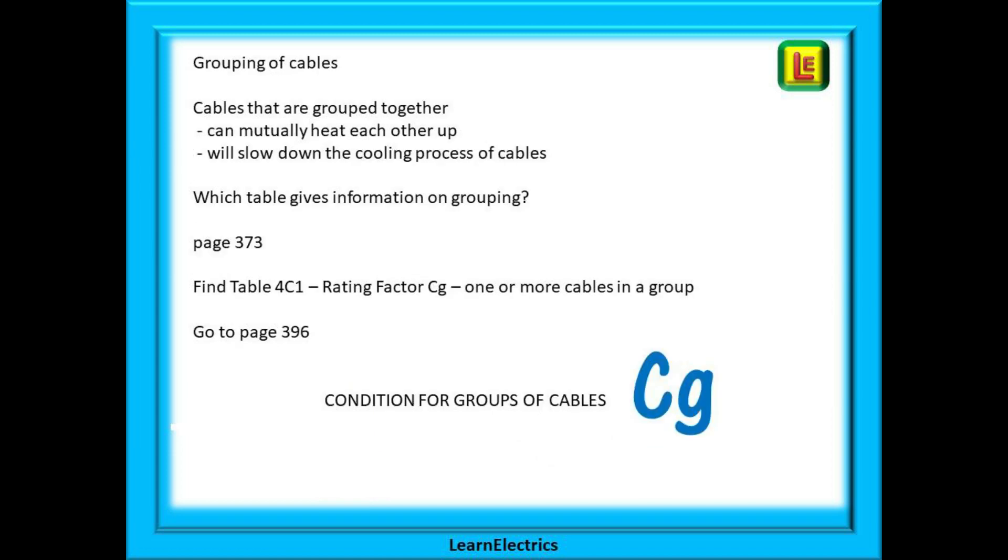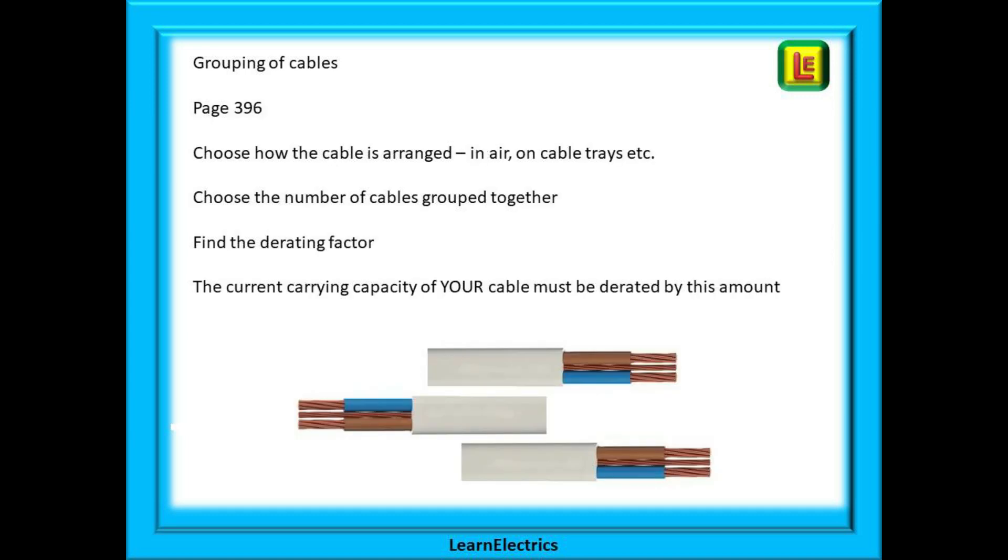Let's look at cable grouping now. We can keep it simple and have just one condition affecting our cable again. Cables that are grouped together can mutually heat each other up and they can also slow down the cooling process of other cables. Which table gives information on grouping? Find page 373 then find table 4C1 rating factor CG for one or more cables in a group. And we will find this table on page 396.